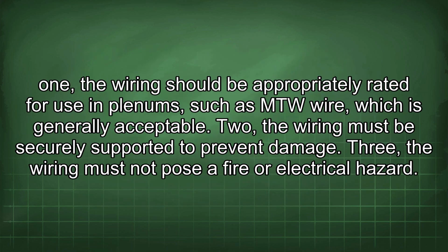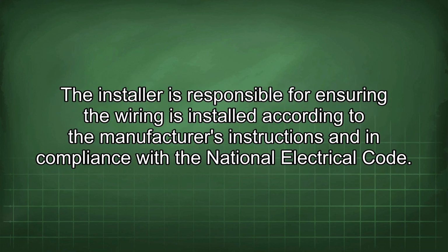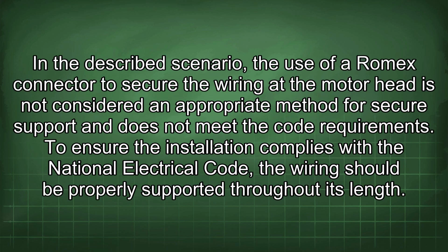1. The wiring should be appropriately rated for use in plenums, such as MTW wire, which is generally acceptable. 2. The wiring must be securely supported to prevent damage. 3. The wiring must not pose a fire or electrical hazard. The installer is responsible for ensuring the wiring is installed according to the manufacturer's instructions and in compliance with the National Electrical Code. In the described scenario, the use of a Romex connector to secure the wiring at the motor head is not considered an appropriate method for secure support and does not meet the code requirements.